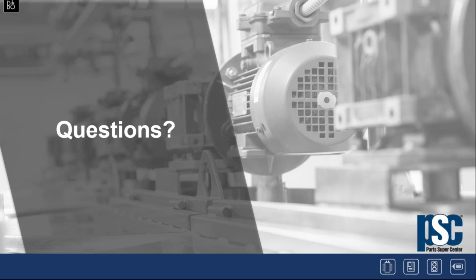That's a very good question. Back in the 60s and 70s, when a DC contactor opens, the coil being highly inductive would tend to put a high voltage spike back in the control circuit. To protect the other devices in that circuit, they would add suppression, basically a resistor-capacitor network attached to the device. A DC contactor with suppression would have this resistor-capacitor mounted to the bottom of the device, and the coil number on the contactor would change to reflect that, generally starting with a 500 series. The purpose was to suppress that spike.